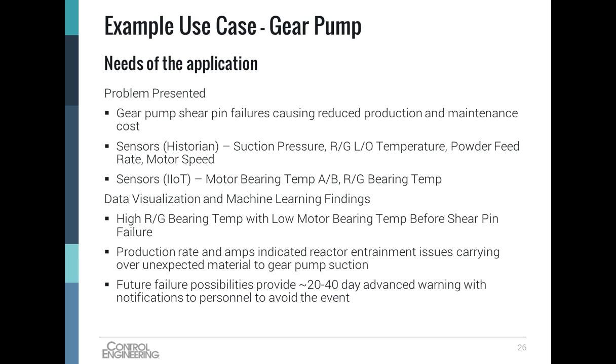The finding was that high bearing temperature of the pump and low motor bearing temperature consistently indicated before the shear pin failed. Production rate and amps indicate reactor entrainment issues, carrying over unexpected materials to the pump.